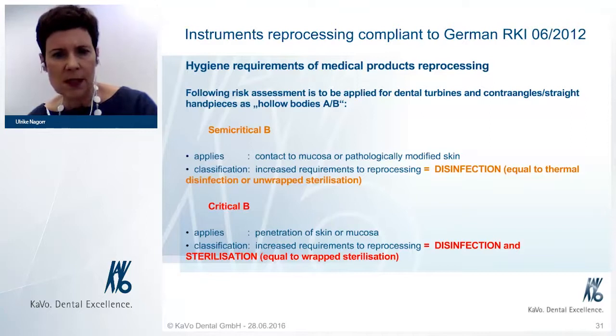What is the difference? What has happened in use to the dental instrument? Semi-critical means the instrument has been in contact with mucosa or pathologically modified skin, and here there are increased requirements for reprocessing that demand a disinfection of the instrument. This could be equal to an unwrapped sterilization or a thermal disinfection in a thermal disinfector.